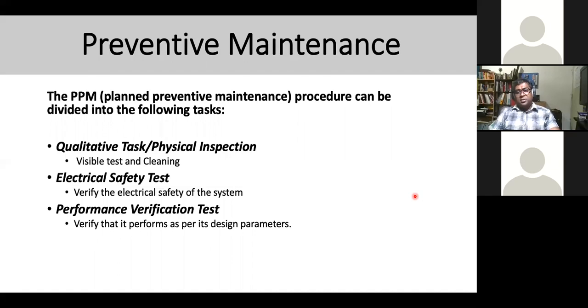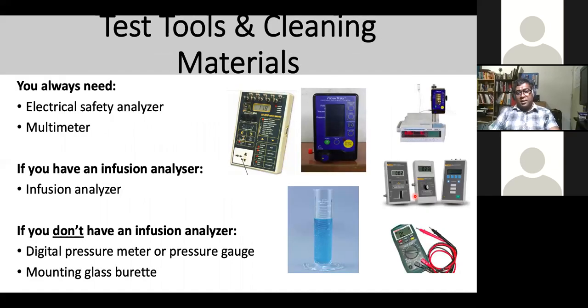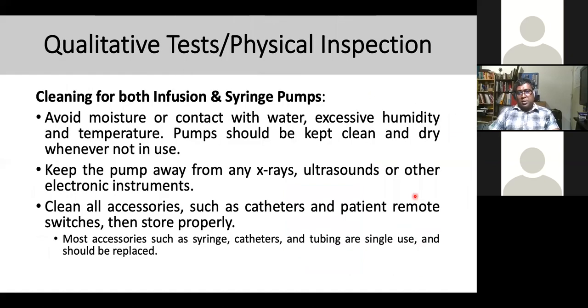So the test tool and cleaning material part of it, you always need an electrical safety analyzer and multimeter when you do all this. If you have an infusion analyzer, then it's easier to do the performance part of it. If you don't have an infusion analyzer, you need a digital pressure meter or pressure gauge and a measuring glass, where the glass type can be 100 ml or 250 ml.